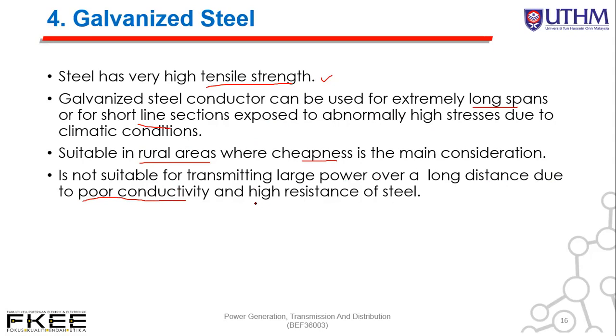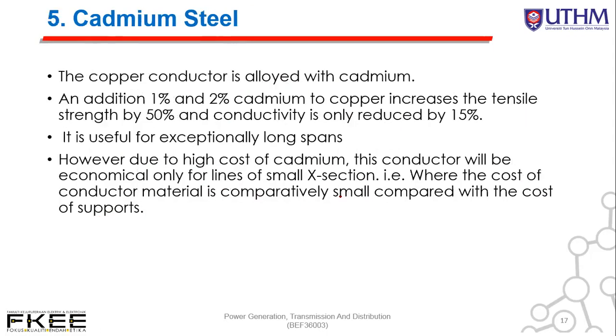Now let's see cadmium copper. The copper conductor is alloyed with cadmium. Adding 1–2% cadmium to copper increases the tensile strength by 50%, while conductivity is reduced only by 15%. It is useful for exceptionally long spans. However, due to the high cost of cadmium, its use is economically justified only for lines of small cross-section where the cost of conductor material is comparatively small compared with the cost of the supports.